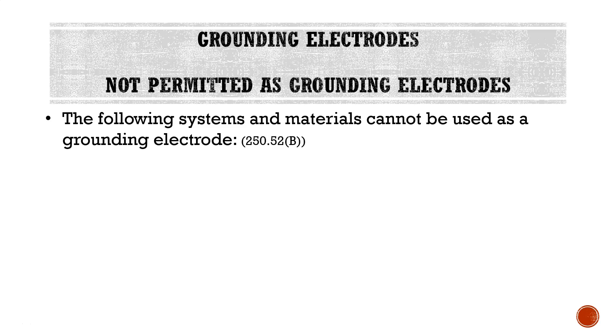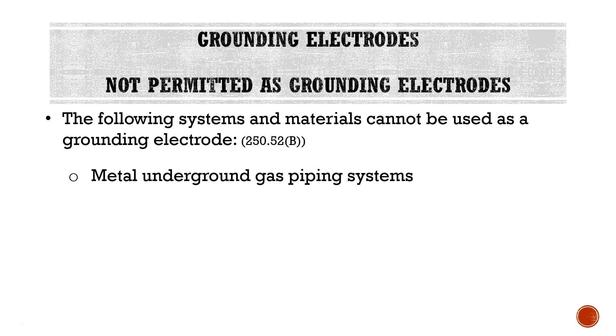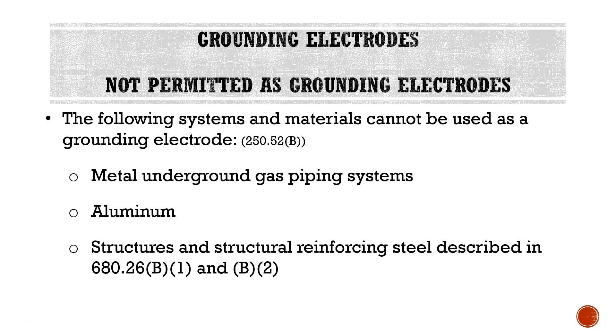There are items not permitted to be used as a grounding electrode. Anything outside the listed types — unless specifically listed as suitable — cannot be used. However, the code gives us some specific things that, regardless of listing or labeling, we cannot use as a grounding electrode. The following systems and materials cannot be used: number one, metal underground gas piping systems. Note that while we cannot use gas piping as a grounding electrode, we are required to bond to metal gas piping — we'll cover that when we discuss bonding. Number two, aluminum. And number three, structures and structural reinforcing steel described in 680.26 B1 and B2.